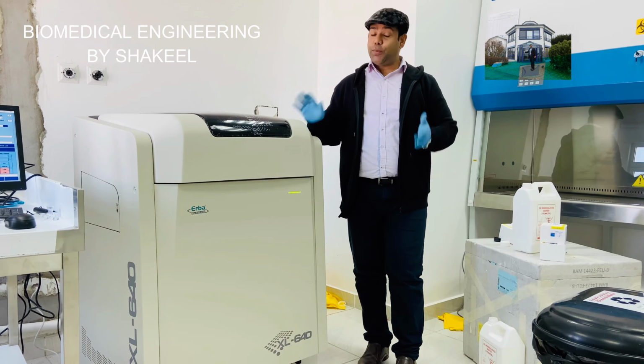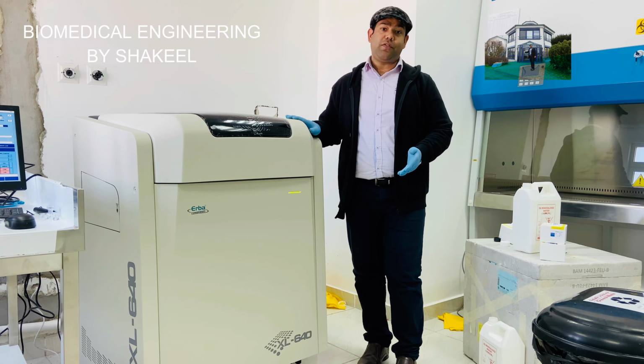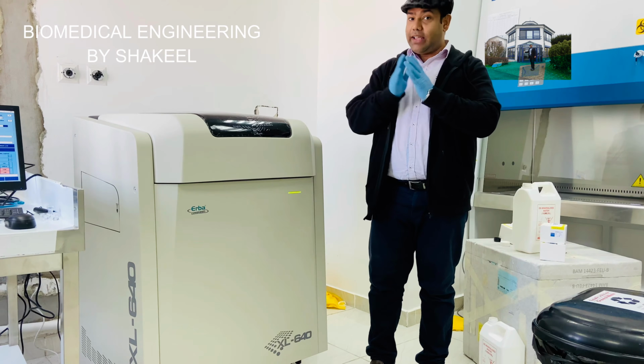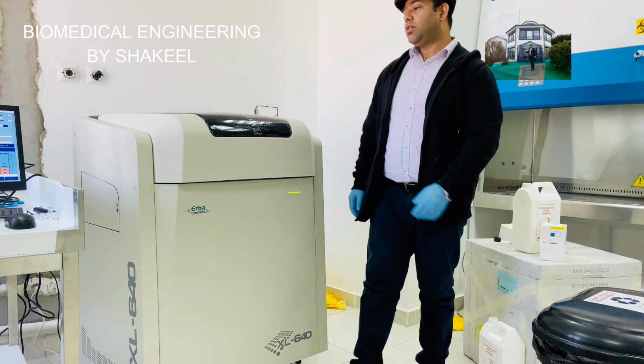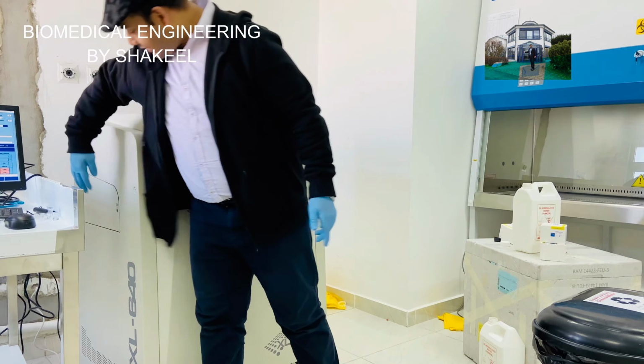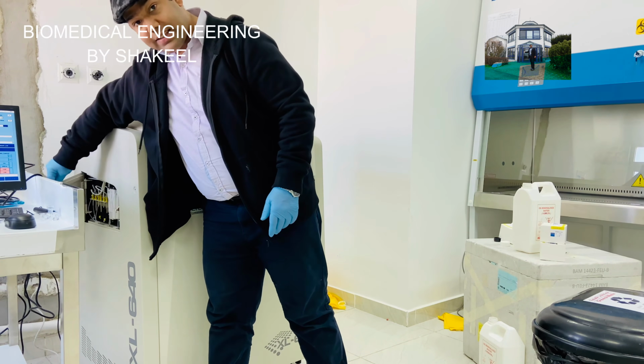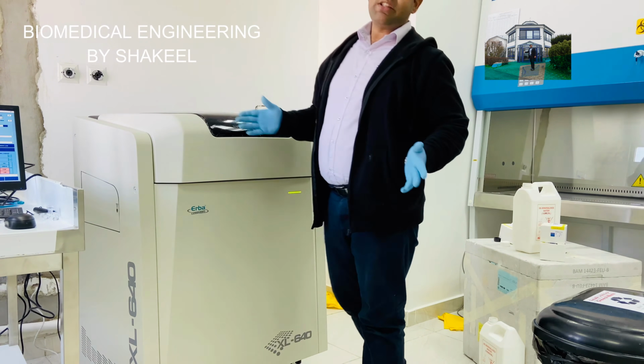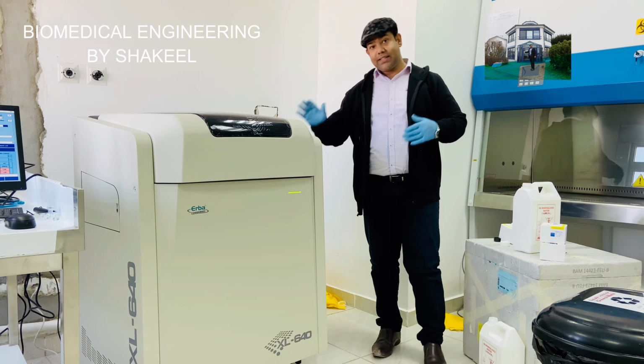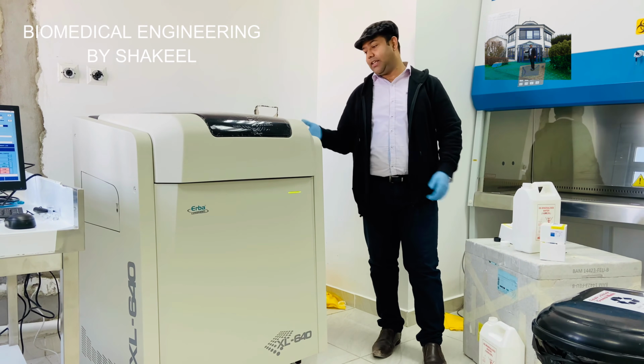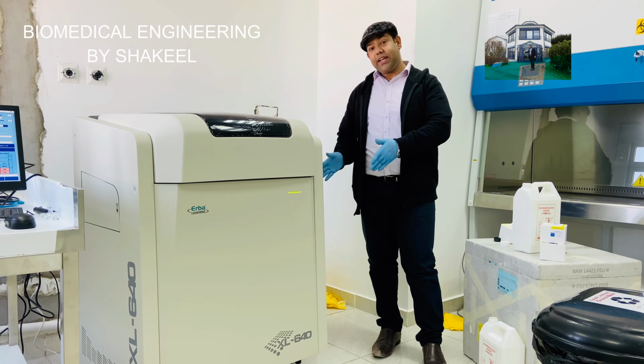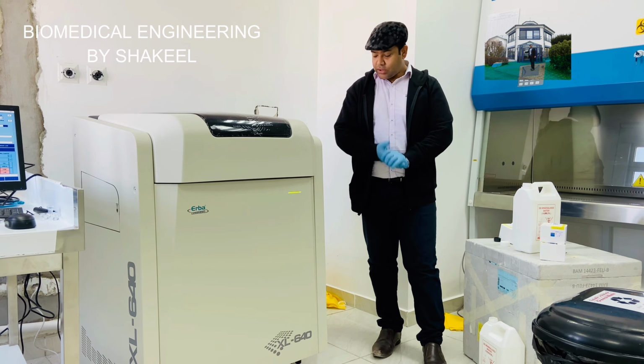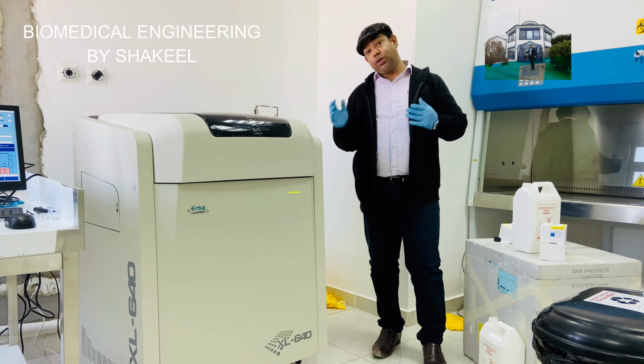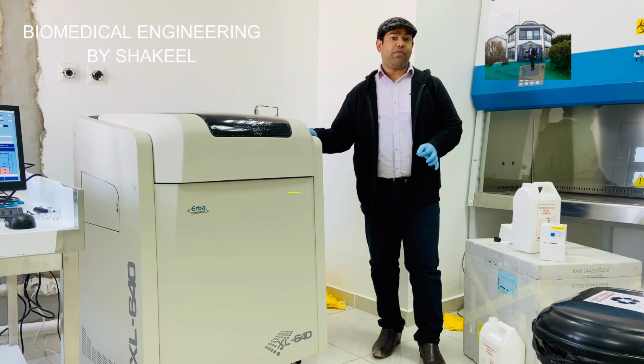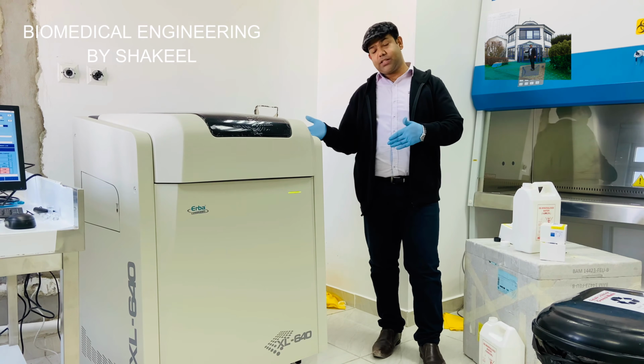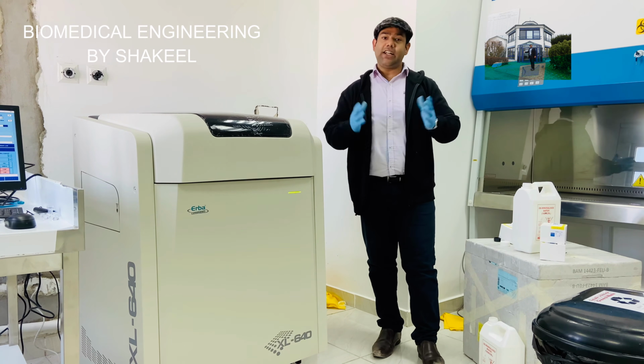Regarding the throughput of this machine, in 1 hour you can perform 640 tests, including ISE. So sodium, potassium, chloride, electrolyte ISE, which is here, is separate. You can see it is separately stored here. All machines are not with the ISE. Some are with ISE, some are without ISE. So this model is along with the ISE. If you talk about the photometric tests, in photometric tests you can perform 400 tests in 1 hour in this machine, including the ISE 640 tests.